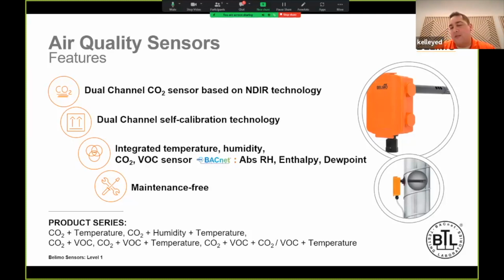But what's nice about this is that within one device, if you opt in for the BACnet version, you get all of these data points with one device. That includes all four types of humidity as well. So potentially 7 or 8 pieces of data with one device, sending info back to your BMS system.